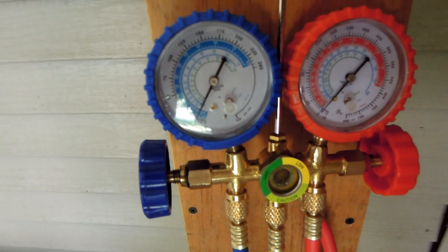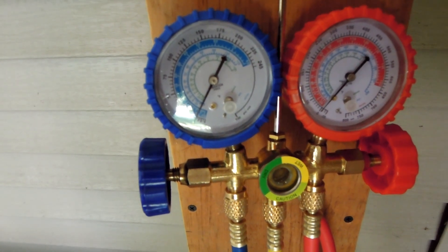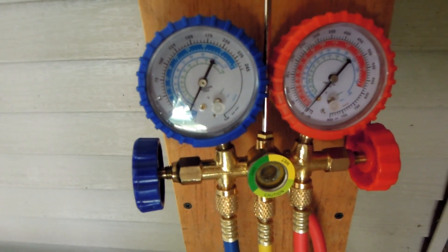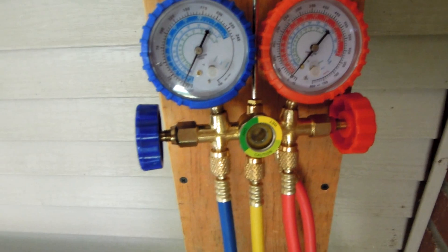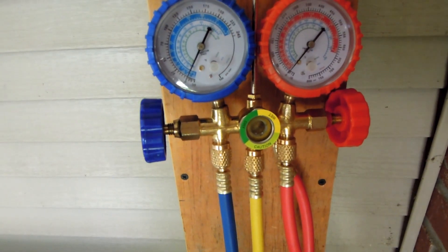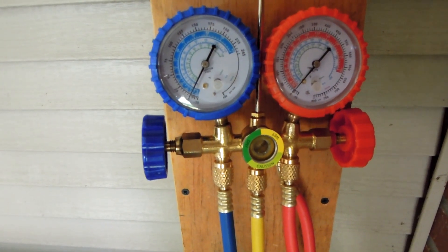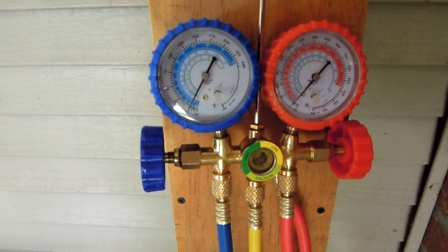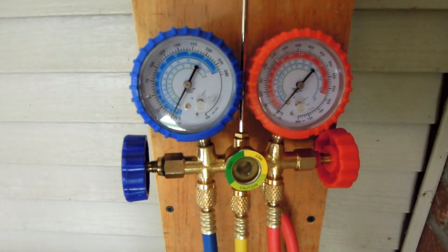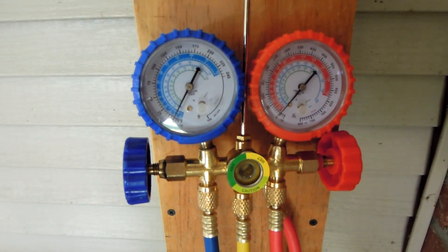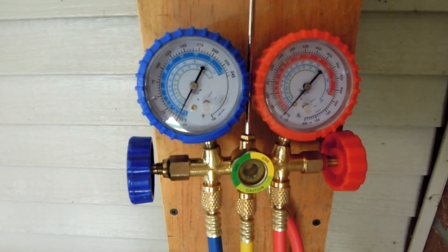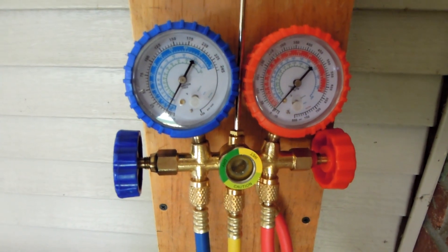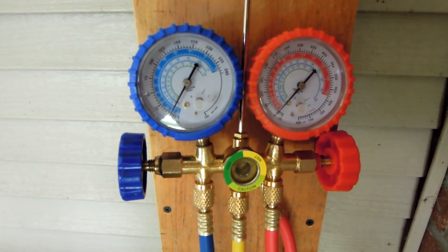What I did was I had something to do, so I actually let it sit at negative pressure. And I disconnected everything and went out to eat. Came back the next day and I was like I had to evacuate again. Plugged it back in. And it was still at negative 30. So I still ran it for another five or ten minutes. And I would say that definitely didn't have any leaks.